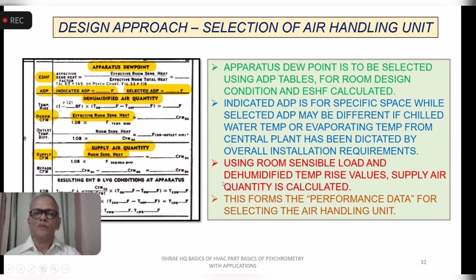Using the room sensible load and the dehumidified temperature rise value, you calculate the supply air quantity. And this forms the performance data for selection of the air handling unit. So we have seen how, from calculation of the load for the space, to go to the performance requirements: the grand total heat, which is the total capacity; the air quality, that's your ADP; and then the air quantity. Then comes the bypass factor, we'll see further. And there is also a factor of sensible heat factor.